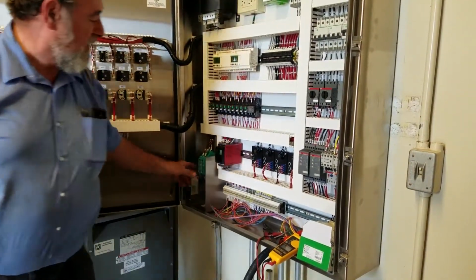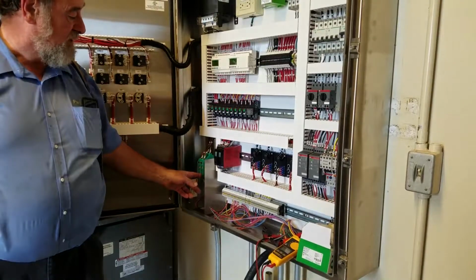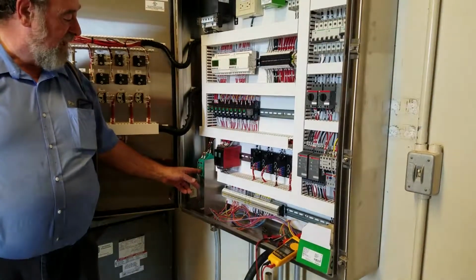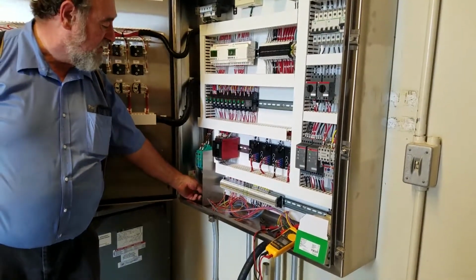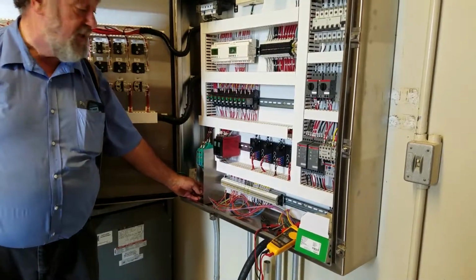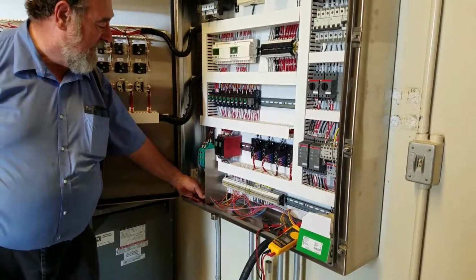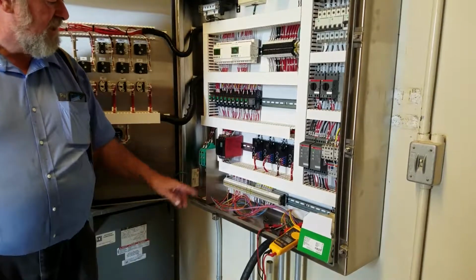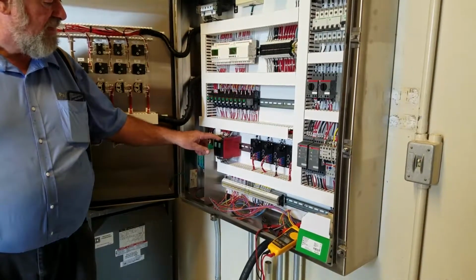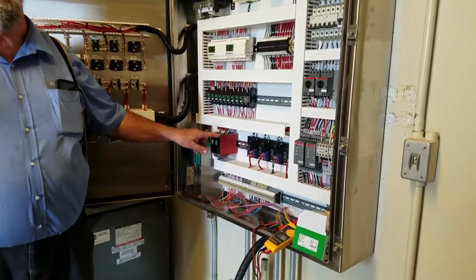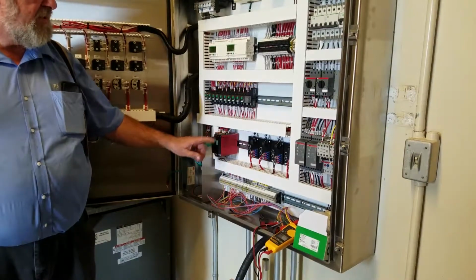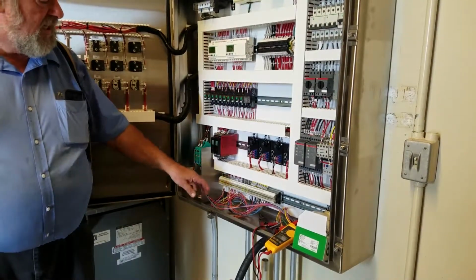Transformer isolation barrier relays that go to your Parkson system. We had a case where this light was flashing all the time. Solution was to switch the 2 leads because it's got polarity requirements. This is the device used to set your level. We still have a problem with a parameter in there because the screen is running continuously, not cycling it on and off.